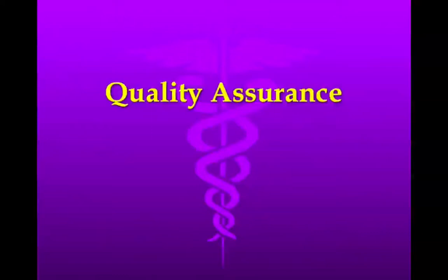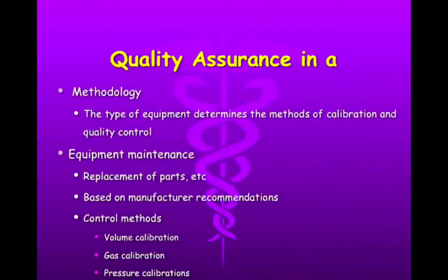When we're doing blood gases, which is often done in a pulmonary function lab as well, we have to do calibrations and quality assurance testings to make sure that our analyzers are measuring all of these things appropriately. Some of the methodologies of quality assurance is that we look at the equipment and we do specific calibrations, and then we test them to make sure that those calibrations are accurate. So we'll analyze a certain gas that we're using, and then the analyzers will test and make sure that that's accurate. Or we will hook up a 3-liter syringe and put air into a machine, and we'll make sure that the value that the machine is analyzing is at or close to that 3-liter amount.